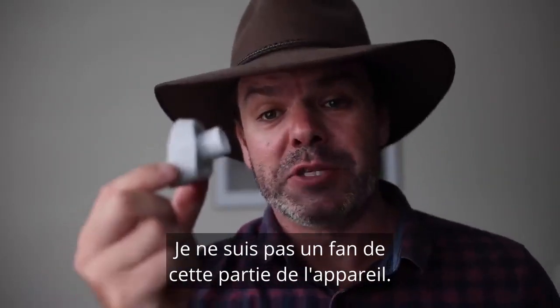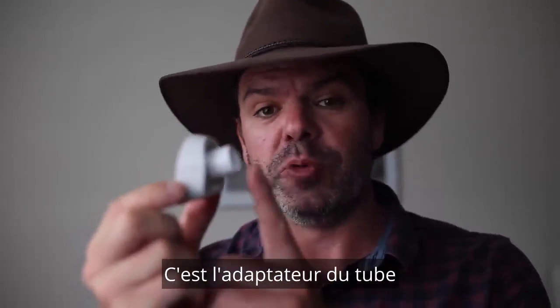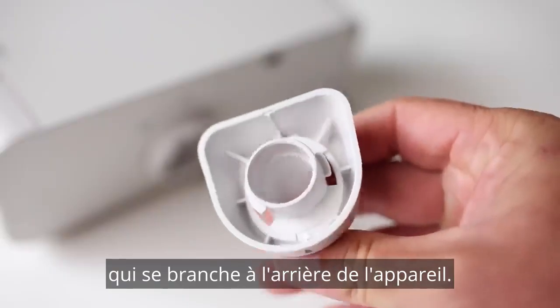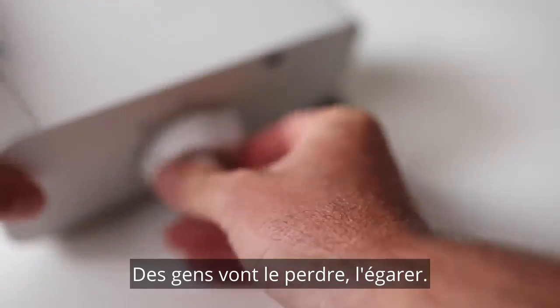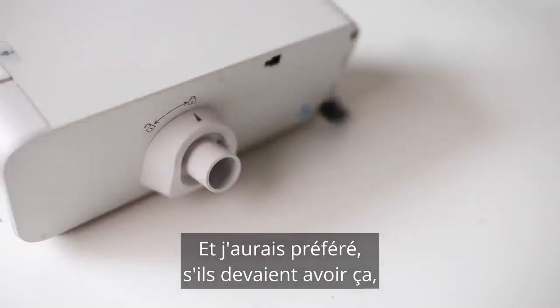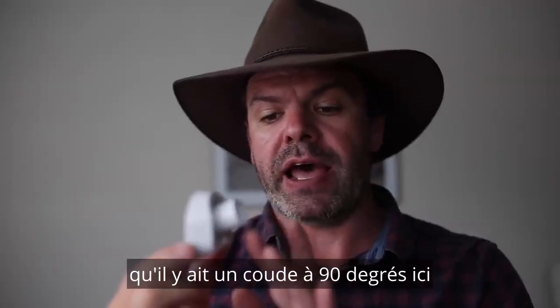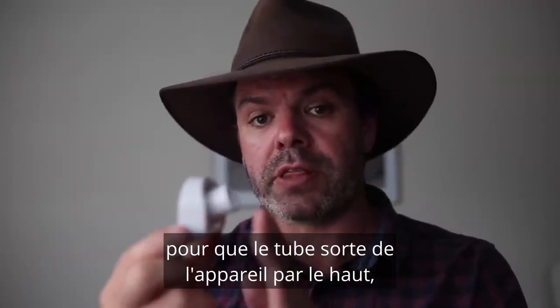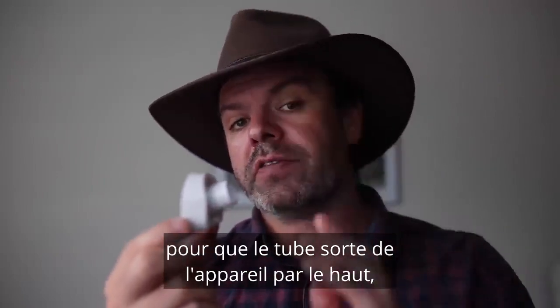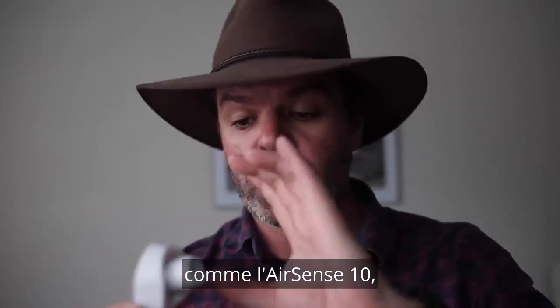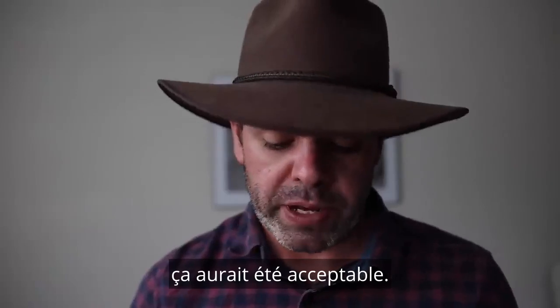I'm not a fan of this part of the device. It's the tube adapter that plugs into the back of the device. I can see people losing it, misplacing it, that's going to be annoying. And I would have preferred, if they had to have this, that it had sort of a 90 degree kink here so that the tubing came upwards out of the device, like the AirSense 10, or if it had a bit of swivel movement, that would have been acceptable.